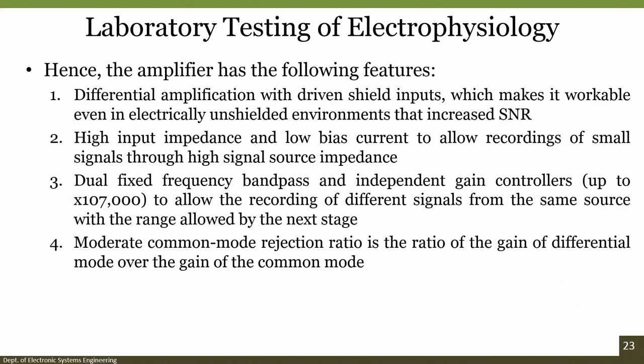So, the amplifier should have the following features when you talk about EEG signal conditioning. The first feature is differential amplification with driven shield inputs, a very important point, which makes it workable even in electrically unshielded environments and increases the signal to noise ratio. The second point is that the amplifier should offer high input impedance and low bias current so that we can record small signals. The next point is dual fixed frequency bandpass and independent gain controllers to allow the recording of different signals from the same source within the range allowed by the next stage. This is required, and that is why we can have the frequency bandpass independent gain controllers up to 107,000. Finally, a moderate common mode rejection ratio, which is the ratio of the gain of differential mode over the gain of common mode, right. You already know it is the differential mode to common mode ratio.